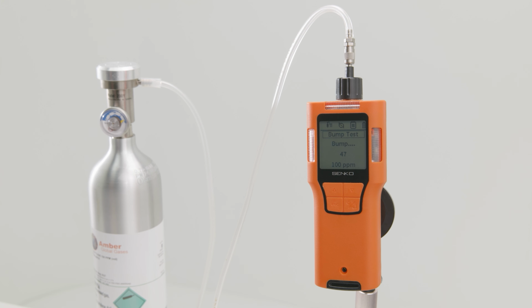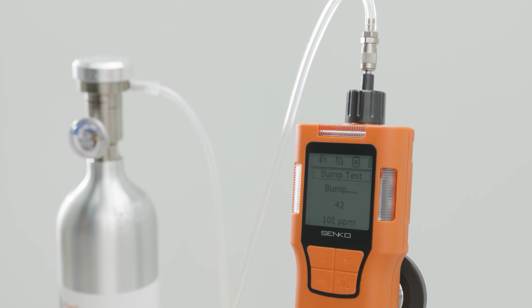The bump test runs for 60 seconds, and if the displayed value is equal to or higher than the low alarm value, it is judged as normal. The test result is displayed as done or fail for about 3 seconds. The bump test interval can also be set from 1 day to 365 days through Senko IR link, and when the interval expires, the bump test icon flashes to automatically notify that the test is required. For accurate and reliable measurement, it is important to perform bump tests and periodic calibration together.